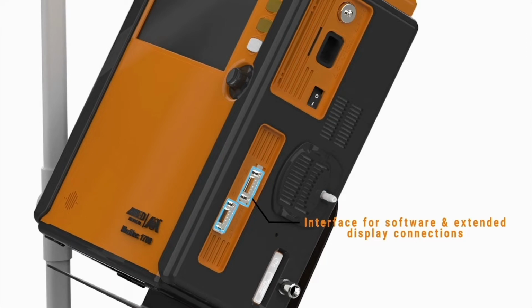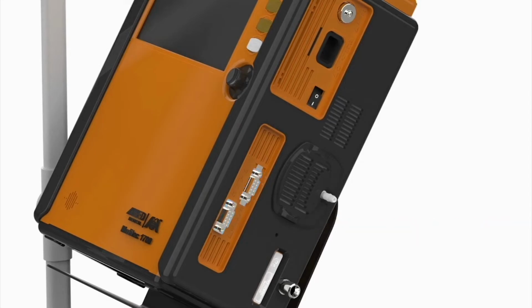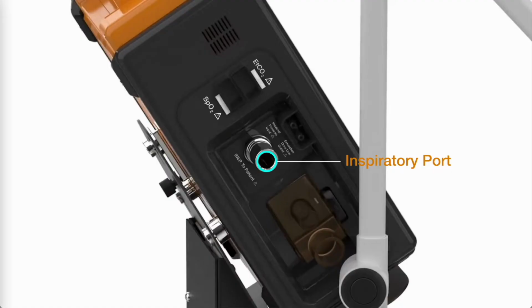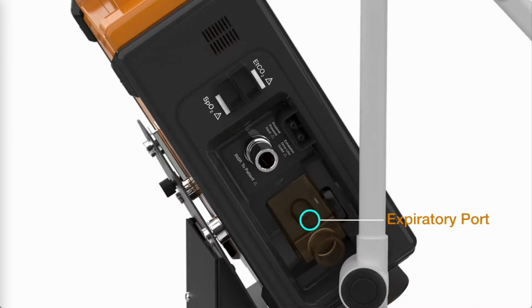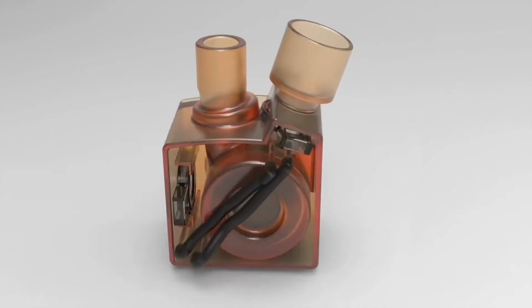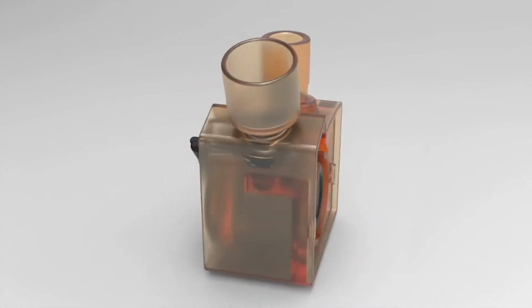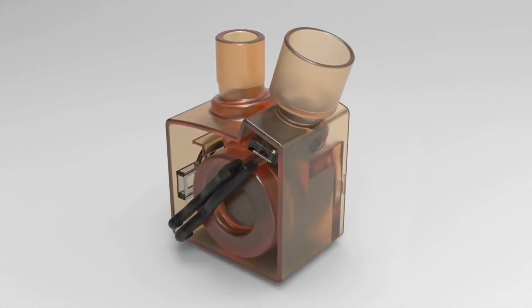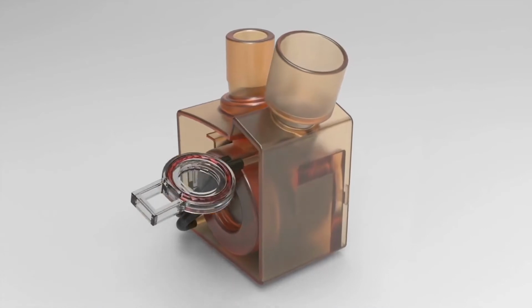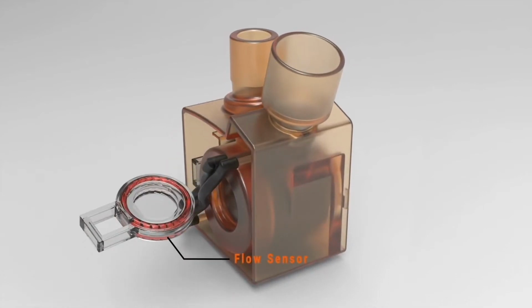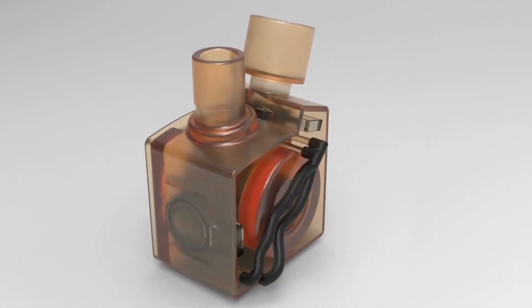If you need an extended display, you could use this interface. On the left-hand side, you have the inspiratory port. The expiratory port is part of the expiratory cassette. This cassette can be plugged out of the ventilator. It could be autoclaved and sterilized to prevent cross-infection between the different patients. Inside the expiratory cassette, you will find two flow sensors, in which one of them is a spare.